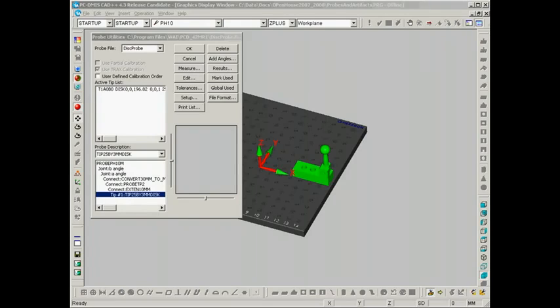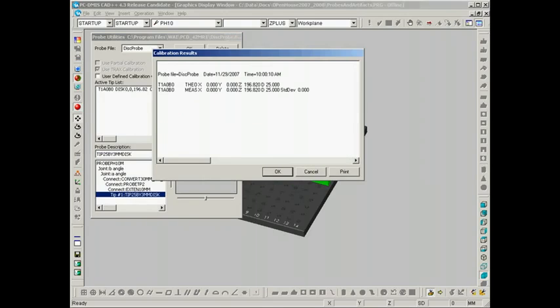And finally, the last thing that we want to do is to ensure that we review the results of our calibration. We're going to look at the size and the standard deviation. The size is most important. Depending on the size of the disc that you choose, you may have to reduce or increase the probing angle in order to get good results. So we want to make sure this size is around nominal.